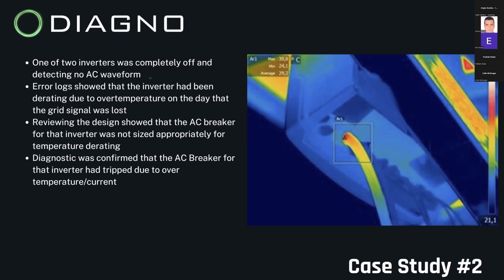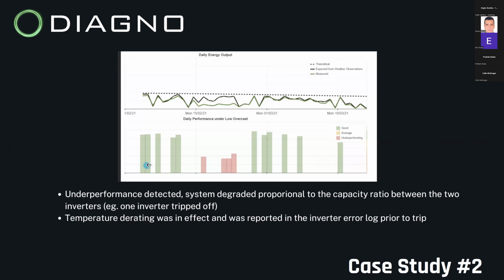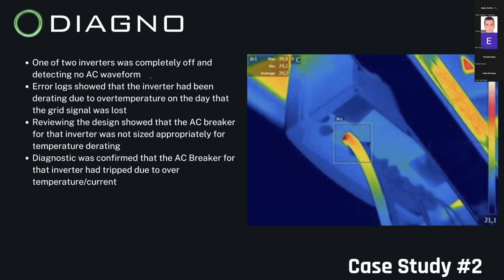And when the facility manager went to check, that was indeed the case, and he flipped the AC breaker back on. And we advised that we should continue monitoring, and if this were to happen again, that they should replace the AC breaker. As you can see, we detected this one quite quickly, and we were able to restore it back to full performance after detection and after liaising with the facility manager.